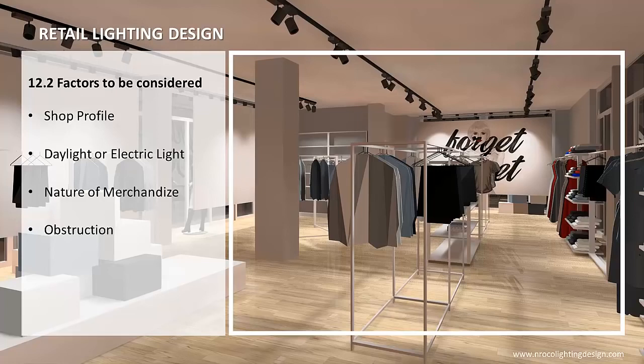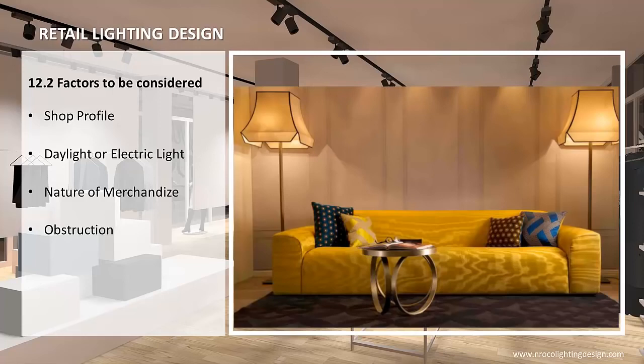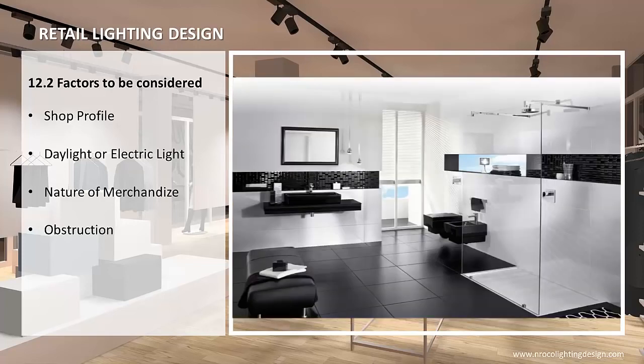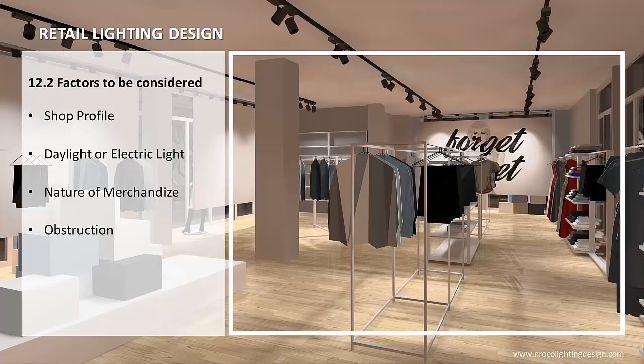Chapter 12.2.3, Nature of Merchandise. The type of lighting and the color properties of the light sources used depend on the nature of the merchandise. Merchandise such as bedding needs to be displayed in a warm, cozy atmosphere. This calls for low light levels and a warm color appearance. Conversely, freestanding white goods are best shown at high light levels with light of a cool color appearance, although when incorporated into displays, simulating a home setting, lighting that looks like attractive home lighting is desirable.